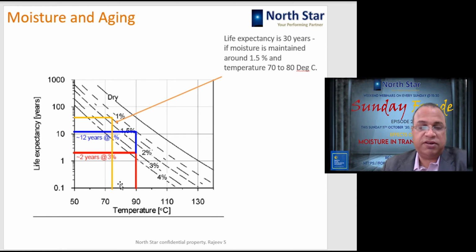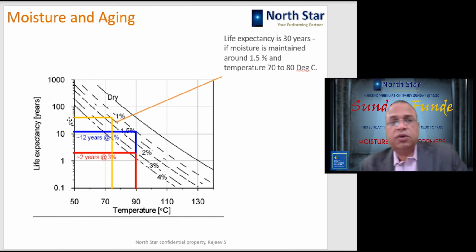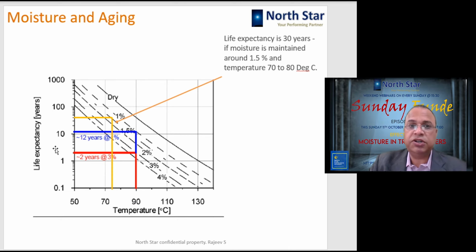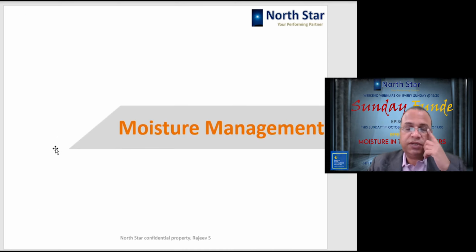Further, if you bring down the operating temperature or load on the transformer, so that it is working only at 80 degrees centigrade or 75 degrees centigrade, then with a 1% to 1.5% moisture level, this transformer will work without any problem for over 30 years. So what I mean to say is, there is a direct correlation between the load on the transformer, moisture in the transformer and life of the transformer. If load and moisture are both kept in check, then the transformer can serve you over a very long period of time without much issue.